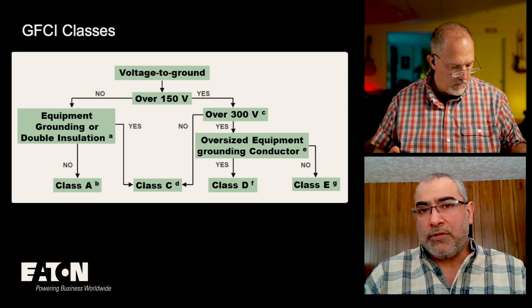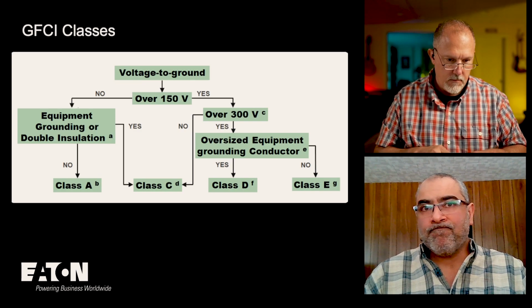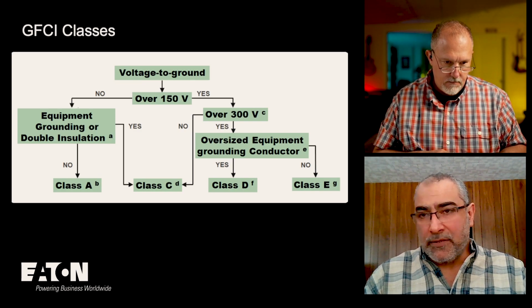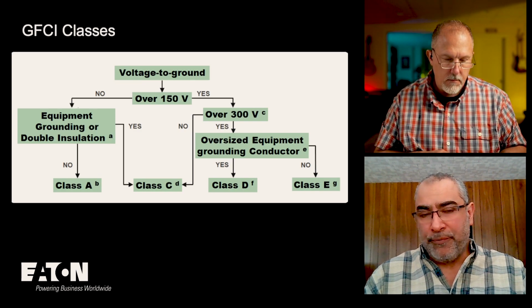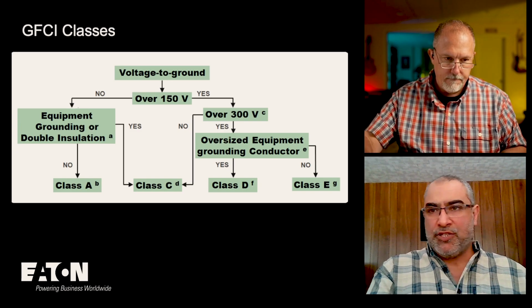If your grounding is compromised for whatever reason, those devices are required to trip, which is something Class A doesn't have. Class A does not monitor your ground. What it does is monitor the current going one way and returning the opposite way, making sure that what went out on the hot conductor returns on the grounded conductor, the neutral in this case, or that the ungrounded and grounded conductors are the same. Perfect, single phase.